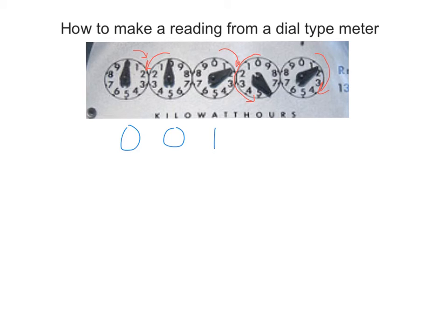The next one up spins this direction. Again, notice going this direction, it's past the 5. It looks like it might be right at the 6, but I'm not quite sure where this actually is. So what I like to do in these cases, when you can't really tell, is go to the next dial over. And here I notice this one is just past the 1.